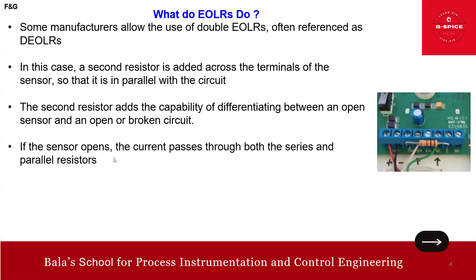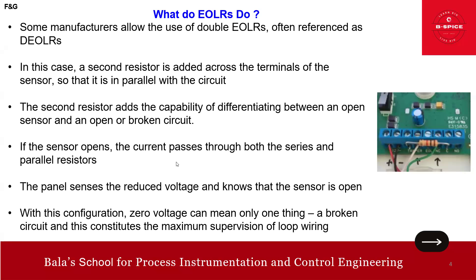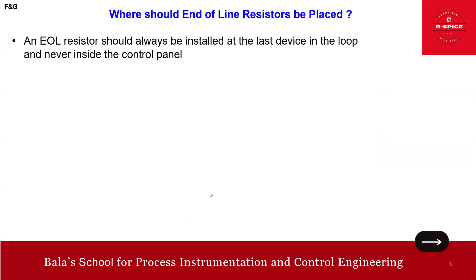The second resistor adds the capability to differentiate between an open sensor and an open or broken circuit. If the sensor opens, current passes through both the series and the parallel resistor, so the panel detects a reduced voltage and knows the sensor is open. With this configuration, zero voltage can mean only one thing — a broken circuit — giving maximum supervision of loop wiring.